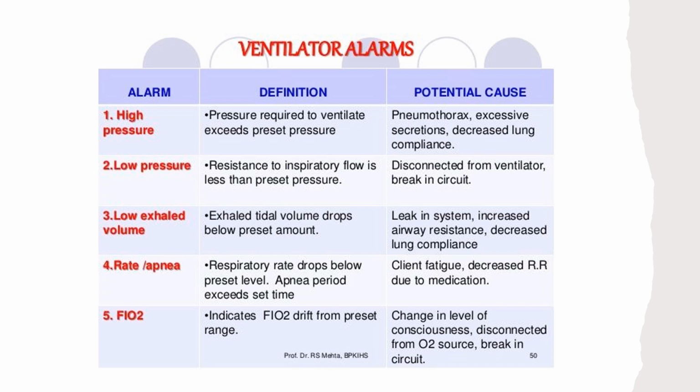Then we have our low pressure alarms, and this is when resistance to inspiratory flow is less than the preset pressure. Okay, so it's not exceeding, it's less. So this is a disconnect. Okay, so the ventilator is disconnected. There may be a break in the circuit.